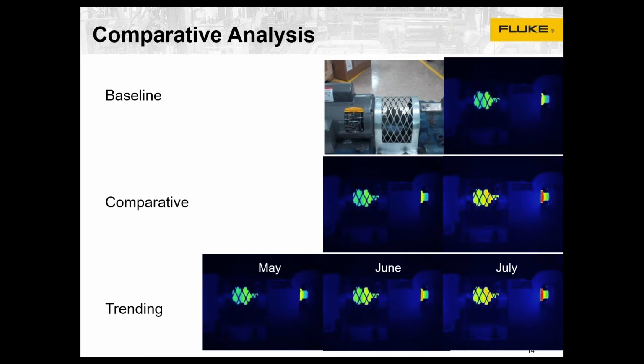From a trending approach, if you capture images and take measurements, you can put temperature markers and trend that hotspot over time to determine when you need to take action and do a deeper dive into the problem with that asset.